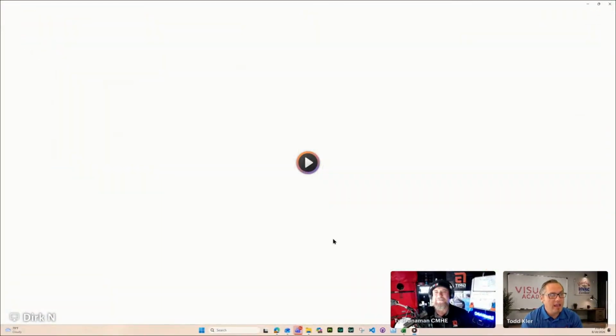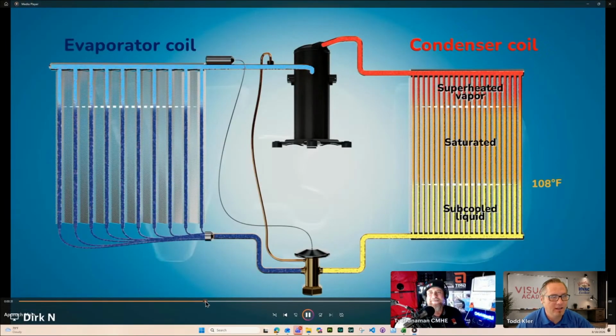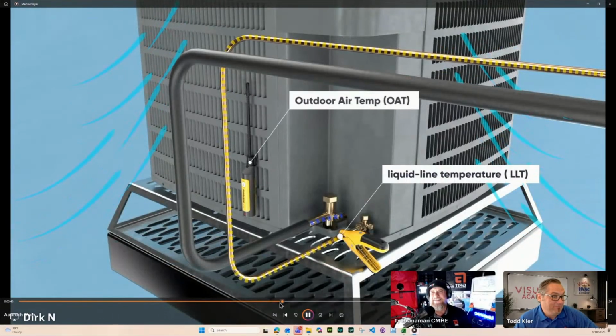But one thing that I know, and that took me a while to understand, is that a higher efficiency piece of equipment, 20 SEER plus, etc., the approach is so close to ambient that there's hardly anything there. And sometimes subcool will be so close, it's hardly there. And it's because that equipment is so efficient. Is that something you recognize too in your career?